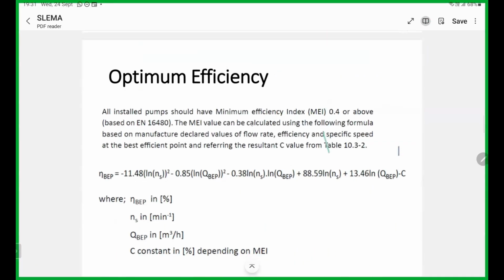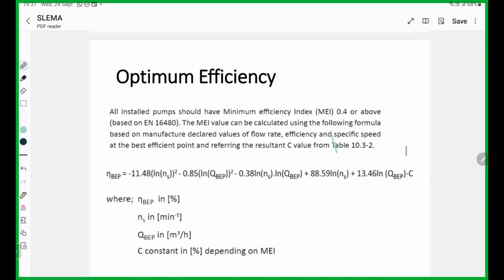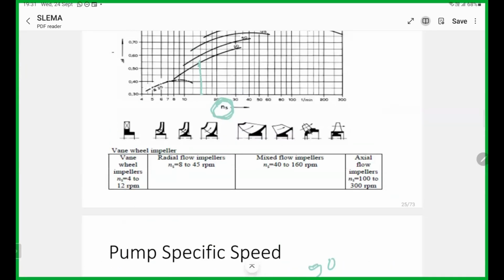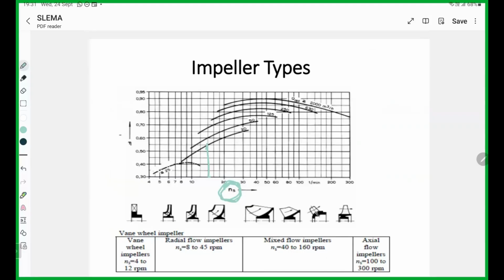Then the most important thing is people, engineers, don't know what the market-available efficiency is. We cannot say pump for pump that it is always more than 50. You see here, in some pump applications we can achieve about 90% efficiency. In some pumping applications we can have only 50 efficiency. You can see here it depends on flow rate and Ns, right? Then actually engineers don't know what efficiency is achievable for their specification preparation, right?